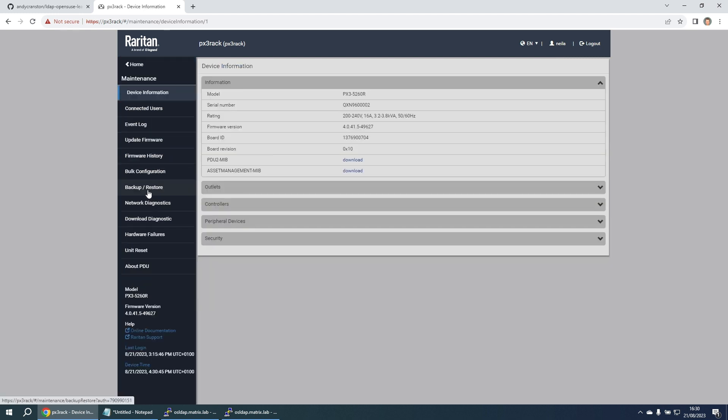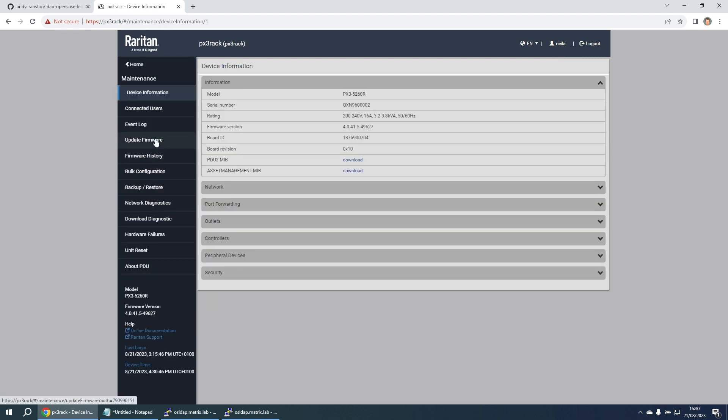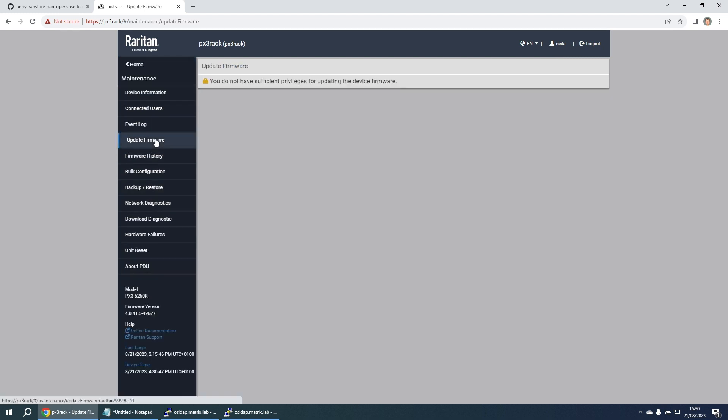Let's go maintenance update firmware again, and this time it's telling us that we don't have the sufficient privileges. So that proves that those two users have got different roles defined in this Raritan PDU. But the upshot is it's proving that the LDAP server is working as we expect.